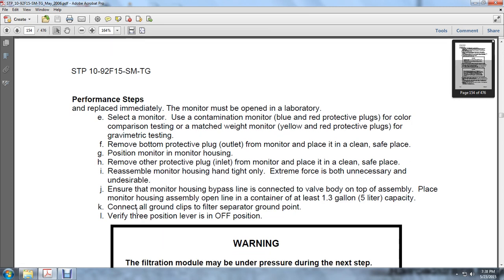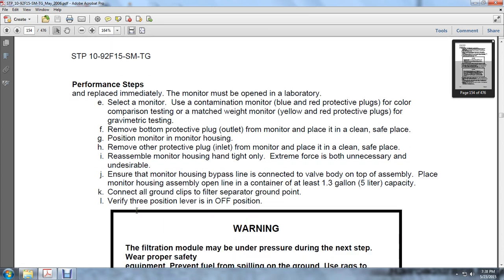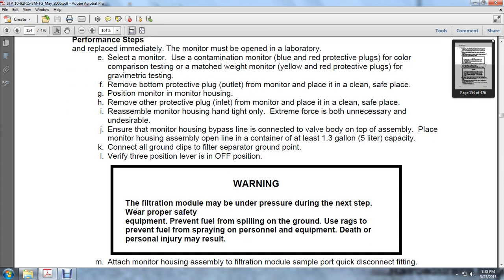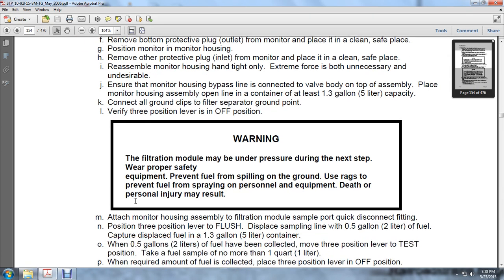Verify that the 3-position lever is in the off position. The filtration module may be under pressure during the next step. Wear the proper safety equipment to prevent fuel from spilling on the ground. Use rags to prevent fuel from spraying on personnel and equipment. Death or personnel injury may result.